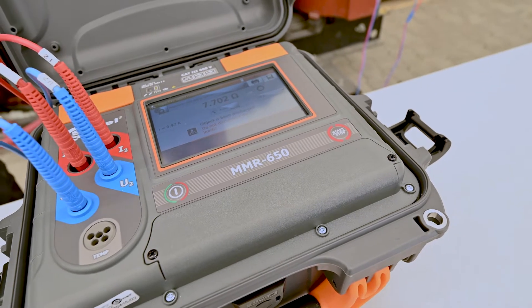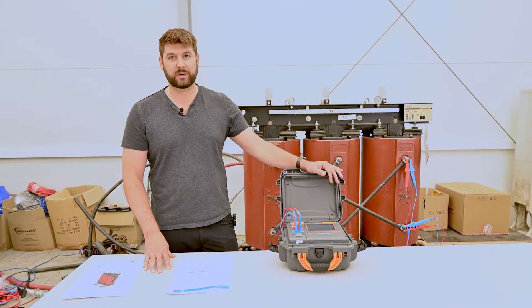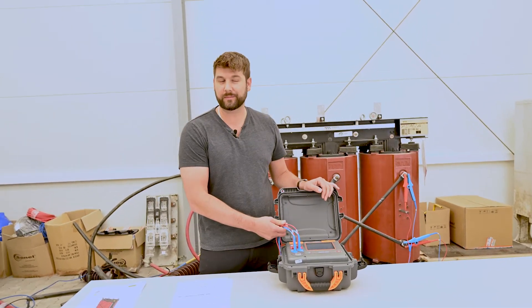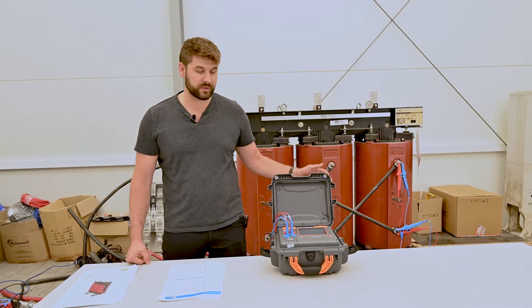And finally we have our third resistance and it's been discharged. This is an example of how you can use a single phase 10 amp micro-ohmmeter with one measurement channel to measure all six windings on a distribution transformer.